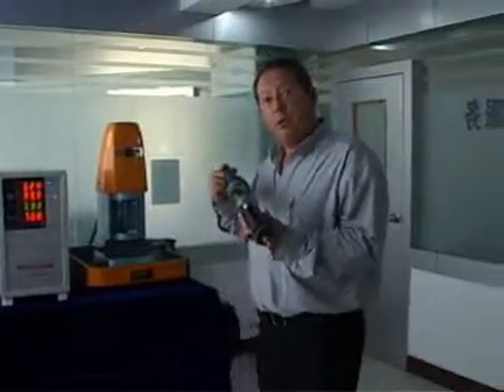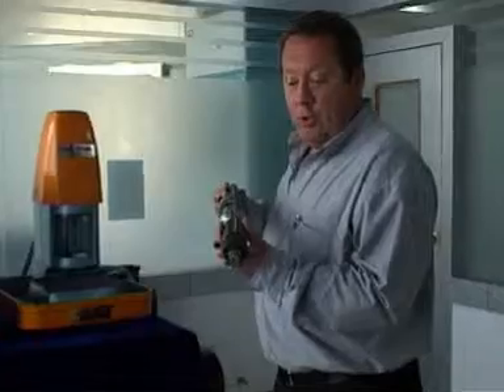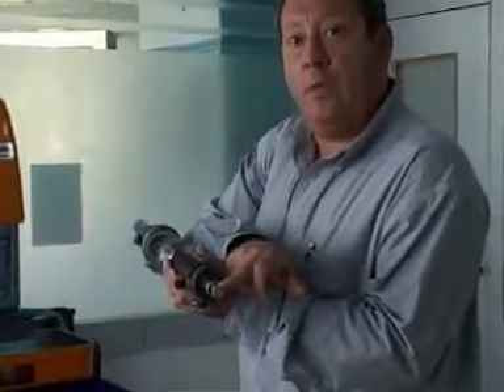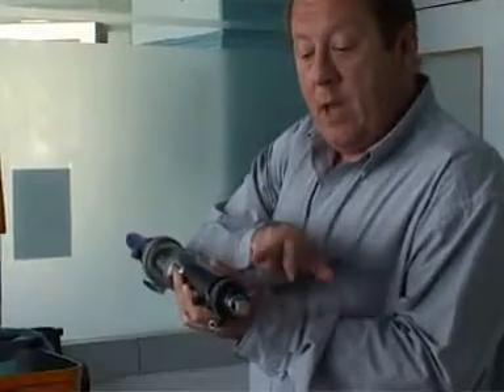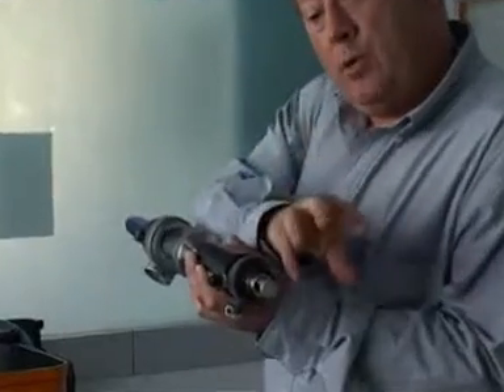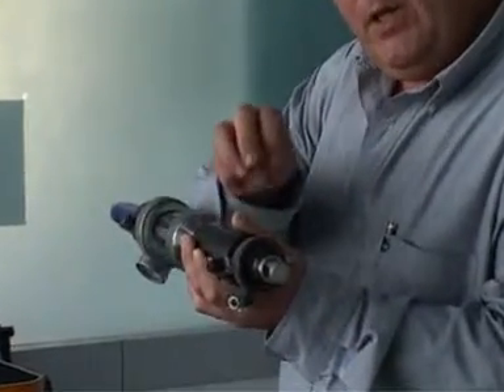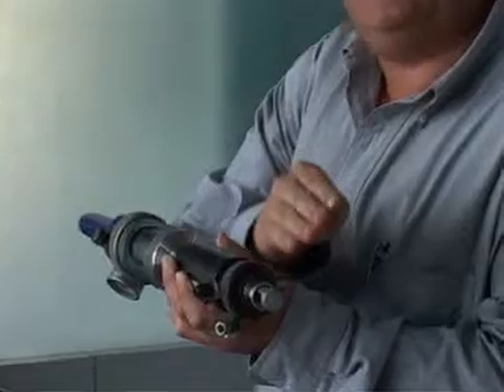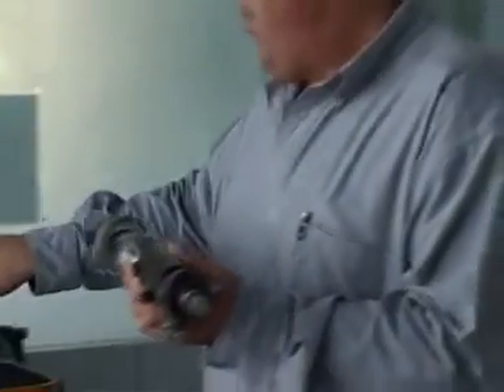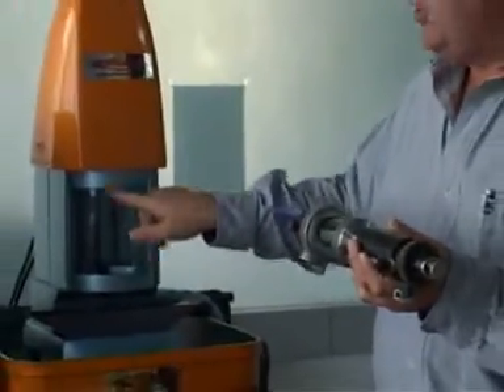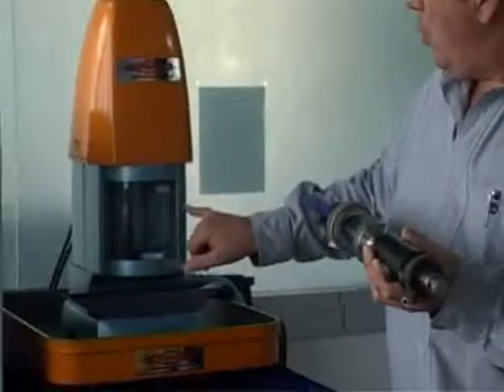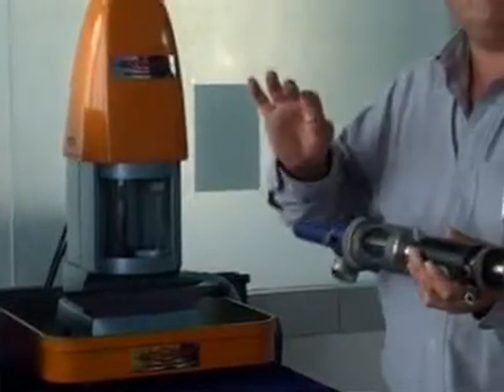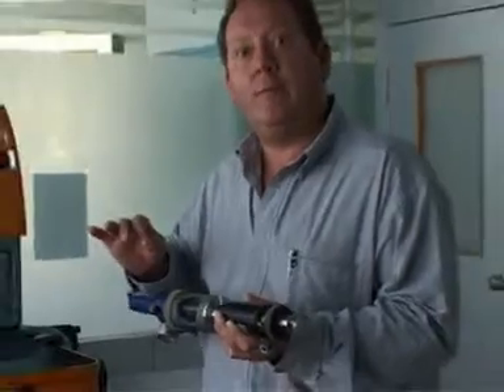Other common devices are used. This is one of the sophisticated probe measuring systems. Very good. It has a glass probe, protected, and a cleaning chamber. So the probe can come into the cleaning chamber, be cleaned, and go back into the measure. But on a 2 probe system, you're always calibrating one against the other to guarantee an accurate reading of pH.